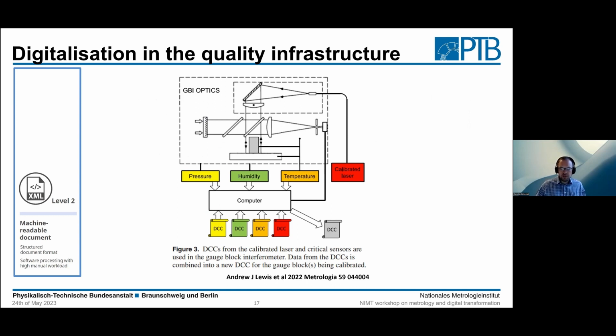Now, again, if you have information in a machine-readable way, you are able to do a high level of automation. And this is one example from an actual metrology set up in place by our colleagues in the United Kingdom, where they have an optical measurement that combines different measuring instruments, like typically the case, and they use digital calibration information from a certificate to have a software in place that automatically adjusts the information, the calibration parameters, the uncertainties. Whenever there's a new calibration, they only provide the certificate to that software, and all the analysis and adoption of the calculations and documentations are undertaken automatically, because the information is provided in a structured format and such as a machine readable document.